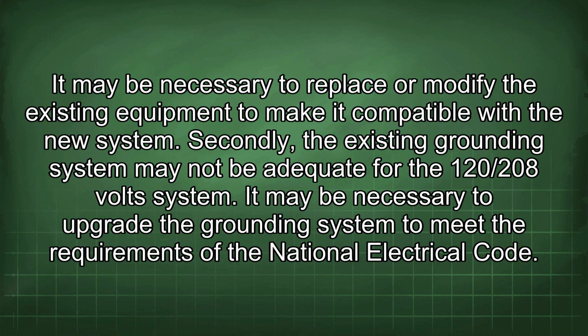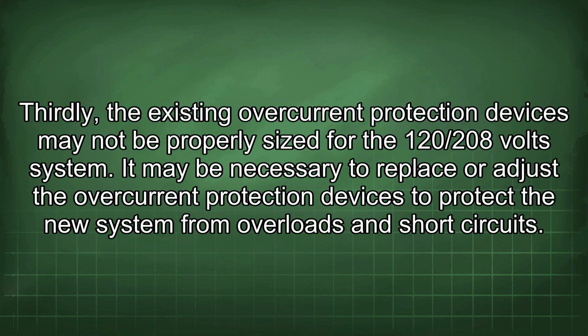new system. Secondly, the existing grounding system may not be adequate for the 120/208 volts system. It may be necessary to upgrade the grounding system to meet the requirements of the National Electrical Code. Thirdly, the existing overcurrent protection devices may not be properly sized for the 120/208 volts system. It may be necessary to replace or adjust the overcurrent protection devices to protect the new system from overloads and short circuits.